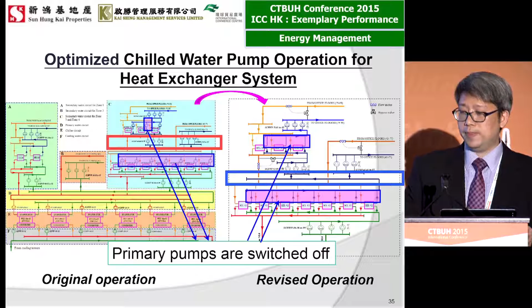Optimize heat exchanger control logic. Originally, the operating speed of pumps distributing chilled water to heat exchangers was controlled by modulating valves. Under the modified control logic, a cascade controller is used instead. The modulating valves are always fully opened so that water loop resistance can be minimized, and in turn, pump energy consumption can be reduced.